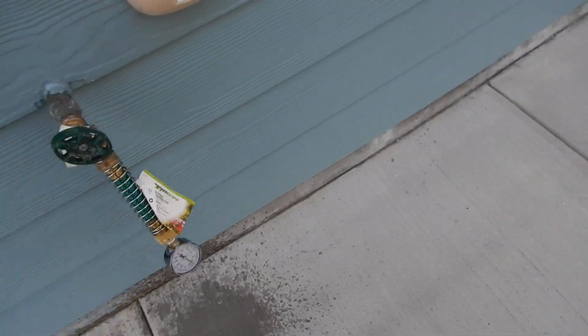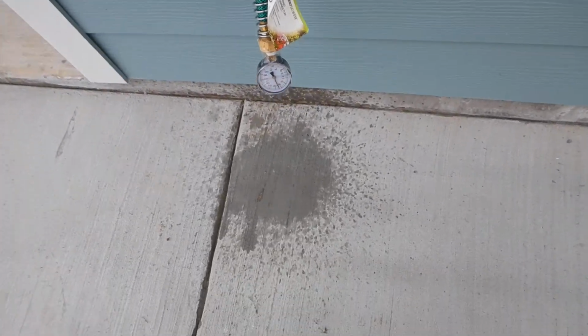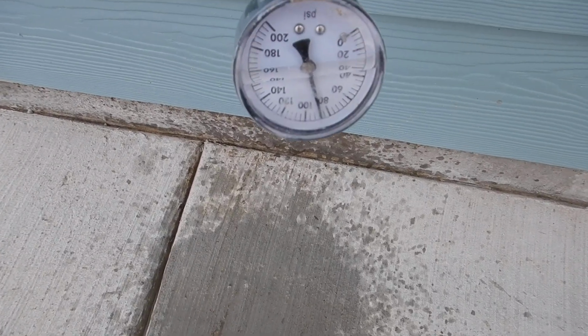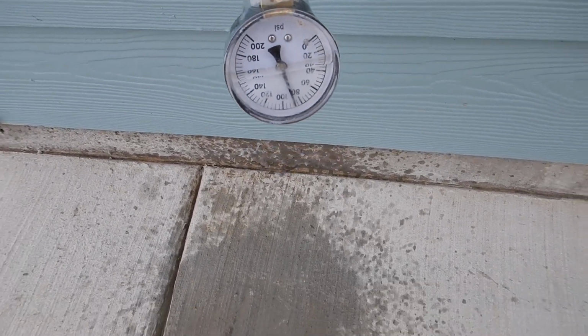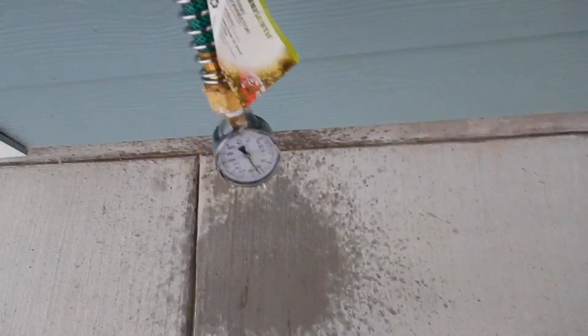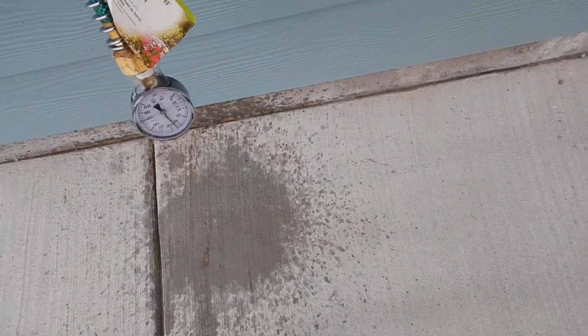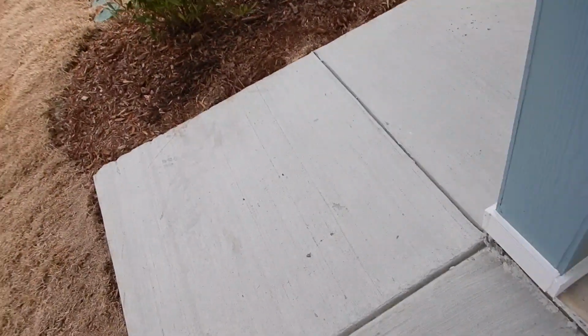Now, on your water pressure, we're looking for between 40 and 80 psi. It shows right here we got about 85 psi, so our water pressure is too high. And it's been on for a while. I'll leave that on, I want to get a still image of it.